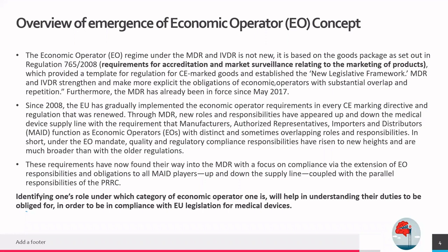Through MDR, new roles and responsibilities have appeared up and down the medical device supply line, with the requirement that manufacturers, authorized representatives, importers and distributors, that is called MAID, function as economic operators with distinct and sometimes overlapping roles and responsibilities. So in short, under the economic operator mandate, quality and regulatory compliance responsibilities have risen to new heights and are much broader than the older regulations.